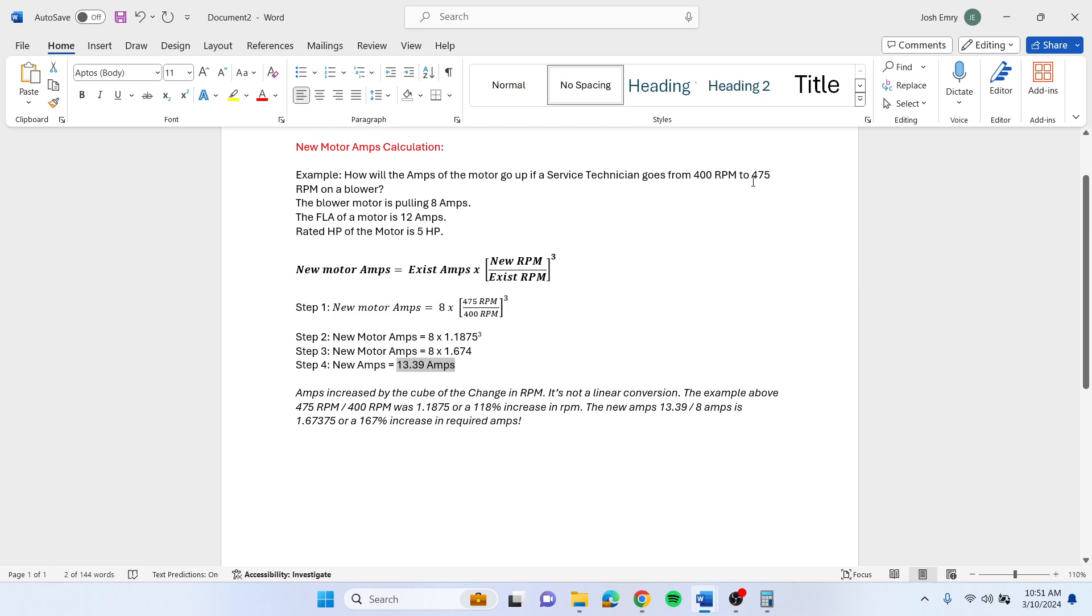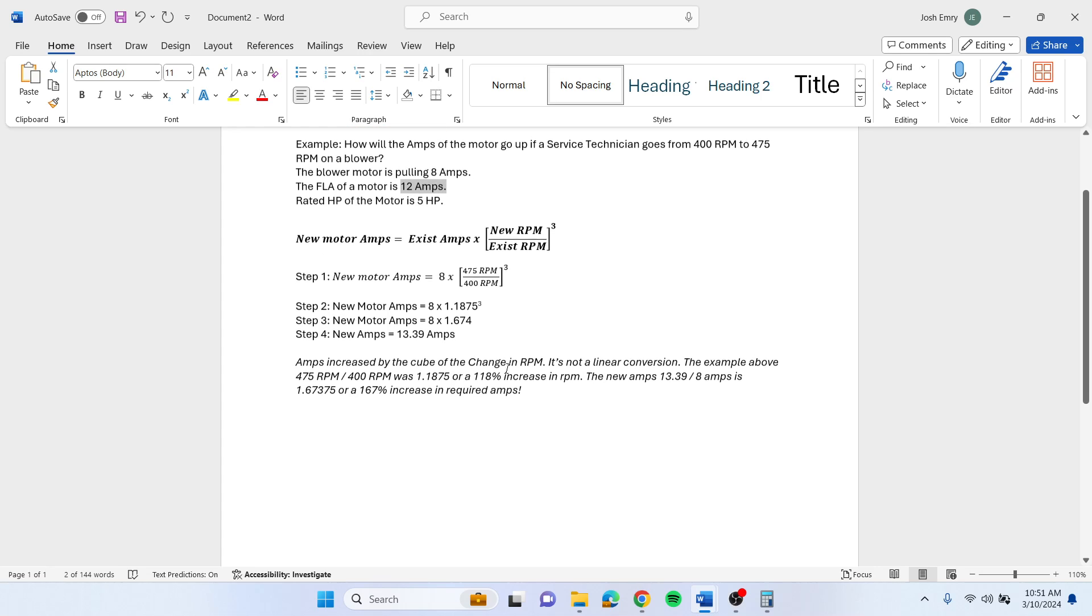So if you just go up 75 RPM, which ends up being an 18% increase, the new amps are going to go up 67%, which then puts you over the motor rated amps. So this motor will not work for that.